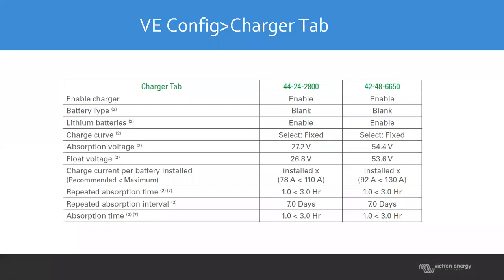All right, we're going to get into the charger tab. We're going to enable the charger. The battery type, we're going to leave blank. We're going to enable the lithium battery, so we check that. The charge curve is fixed. The absorb, we're going to set to 27.2 and 54.4, just like on the other. The float, 26.8, 53.6. And the charge current per battery installed, 110 amps for the 24 volt, 130 amps for the 48 volts, and that would be per battery.